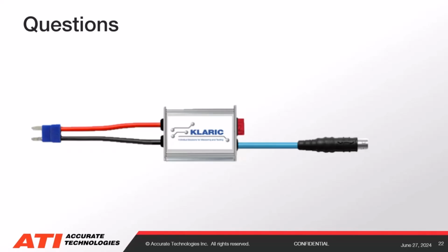So you have to do nothing, just put the probe in. Automatically we send the data, but we also send the probe type into the ATI software. The ATI software knows, okay, when it is this probe, I need this scaling factor, when it is this probe, this one, and automatically it will recognize this and change it without any changes from your side. So you configure this once, the first time when you install the system, and after this, you just use it.